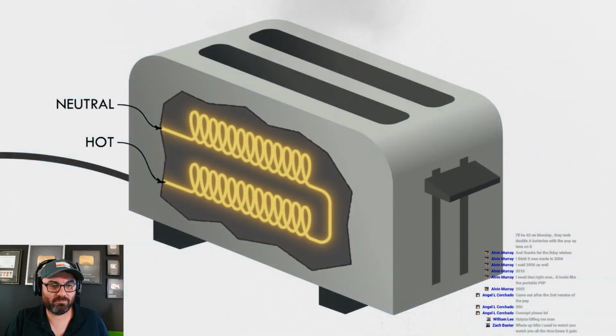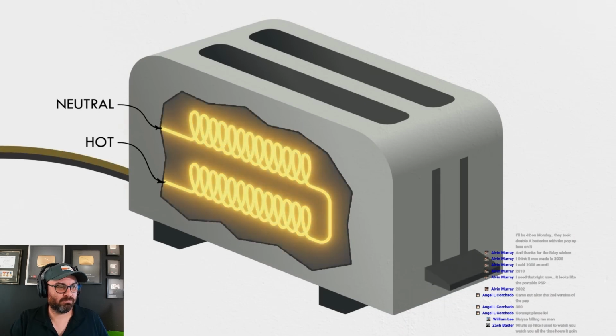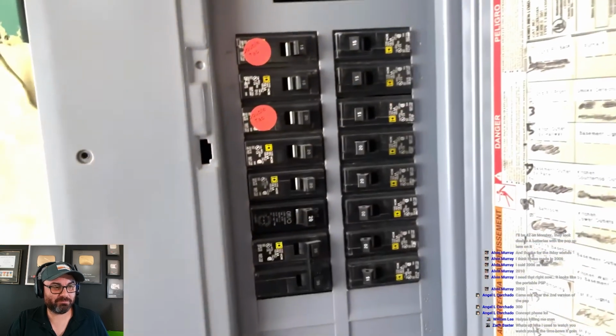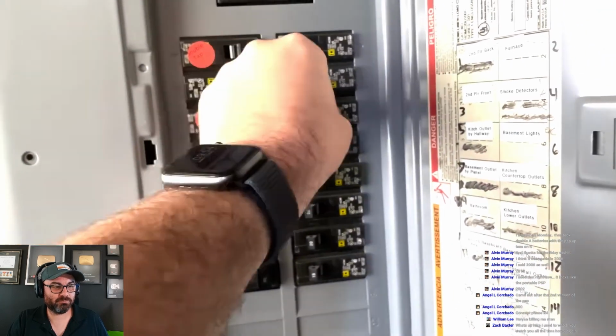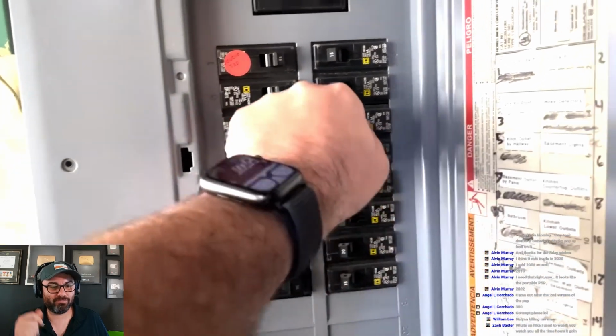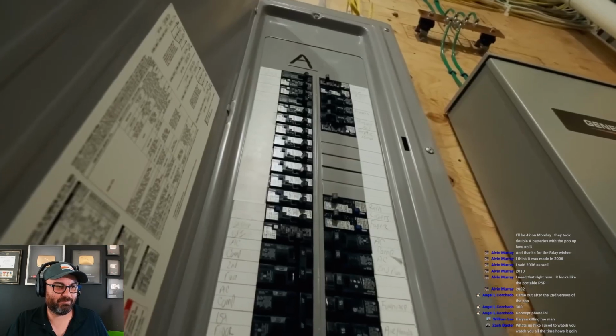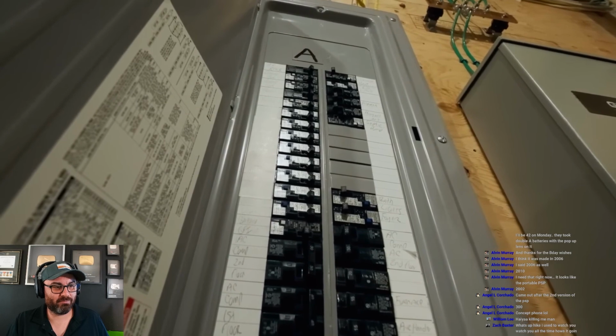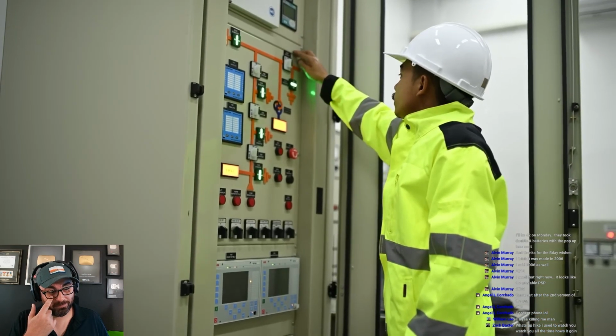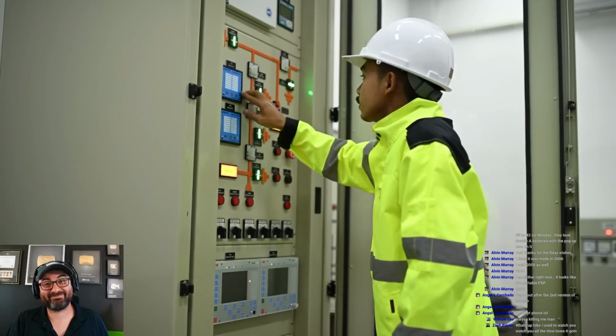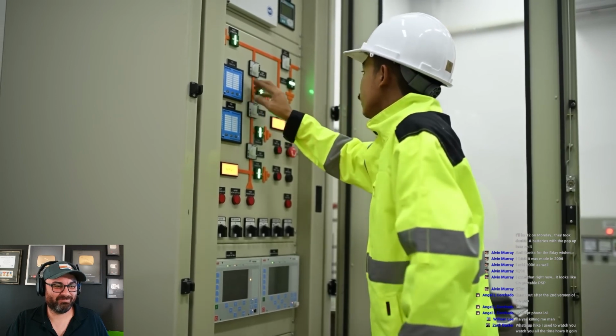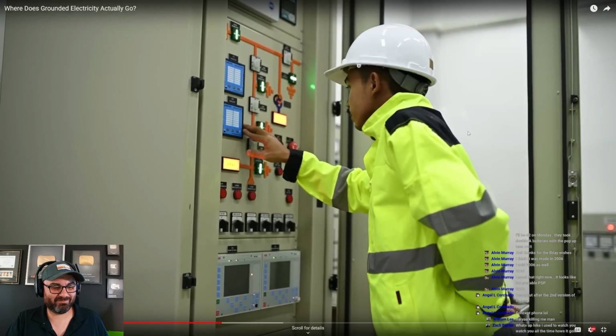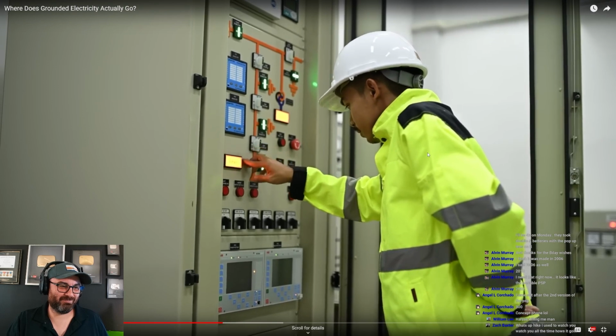So many appliances are required to have another conductor attached to the housing, giving the current a parallel low resistance return path. Yep. That low resistance means lots of current will flow, triggering a breaker to shut off the circuit. Yep. And it's not just the breakers in your house that work this way. Nearly all the protective devices, called relays, that monitor parts of the power grid for problems rely on fault current to tell the difference between normal electrical loads and short circuits.